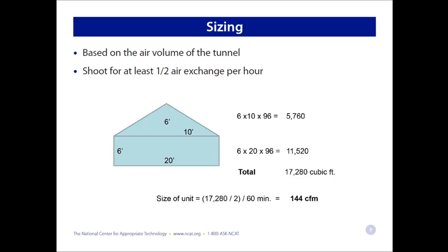Sizing the unit is fairly crucial. I was guessing at sizing the unit because I had not found any information on this being done before, or these units being used to ventilate a high tunnel of this size before. But it's all based on the volume of air in the high tunnel. The units are sized by CFM, or cubic feet per minute of air that they can move. And you need to base that sizing on the volume of air that you're trying to move.